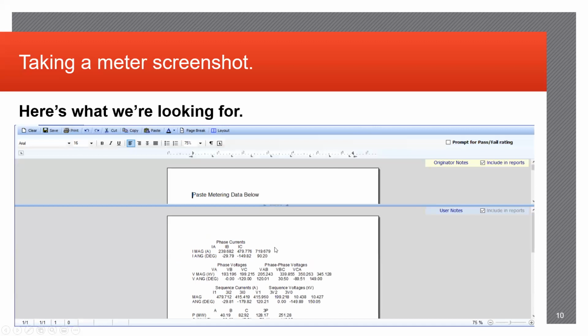So an example here, this is a copy and paste from the metering command from the relay terminal that we were talking about earlier. So the test engineer put in different values for each phase for the voltages and currents, and correctly identified that the previously calculated ratios match up with what should be seen on the relay. And once that's done, you can confidently verify that your ratios and measurements will be correct going forward when doing the rest of your testing.